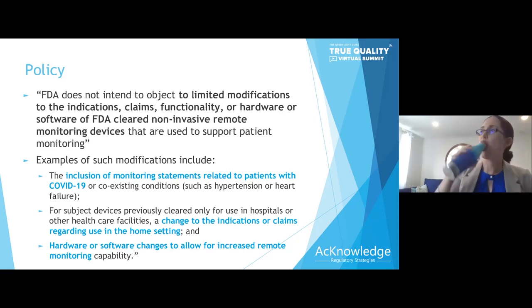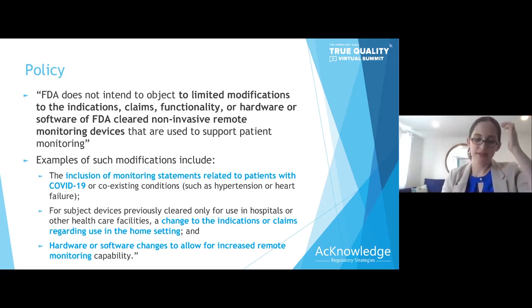All right, so a little bit about the policy. FDA has stated in this guidance document that they do not intend to object—and I know that's sort of a funny way of putting it, but hear me out—to limited modifications of the indications, claims, or functionality of the hardware or software of a cleared device. So if you want to modify the indications of your device, say one used to support patient monitoring, that is acceptable, and that's what's contained in this guidance document.